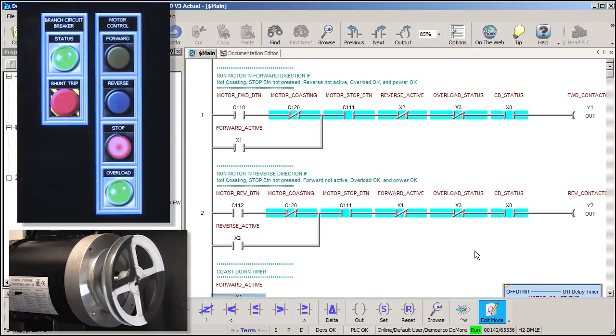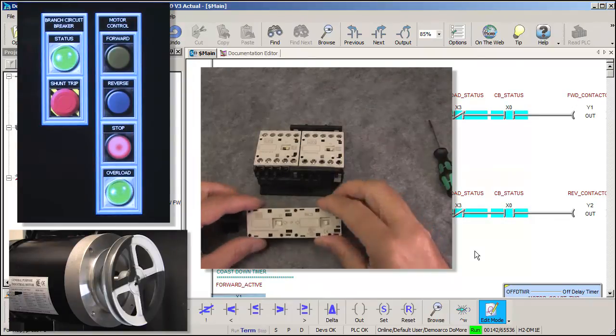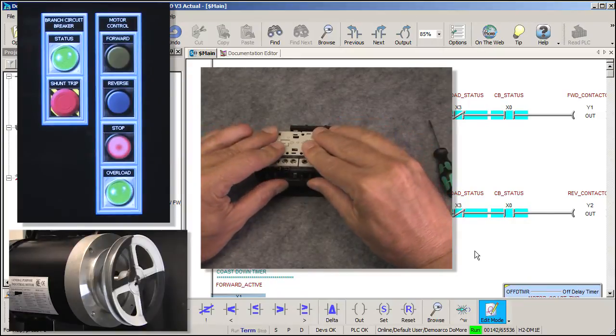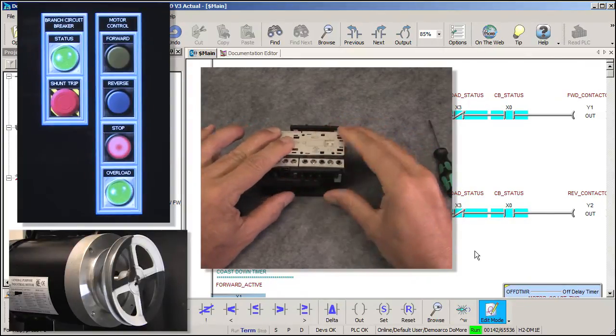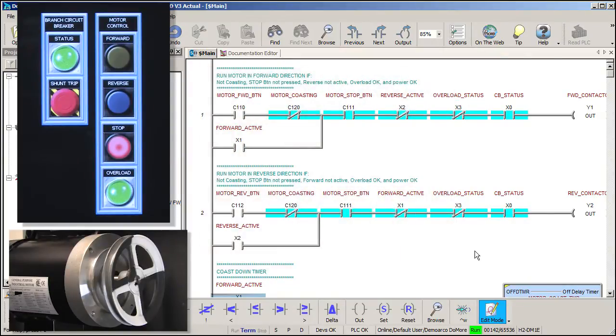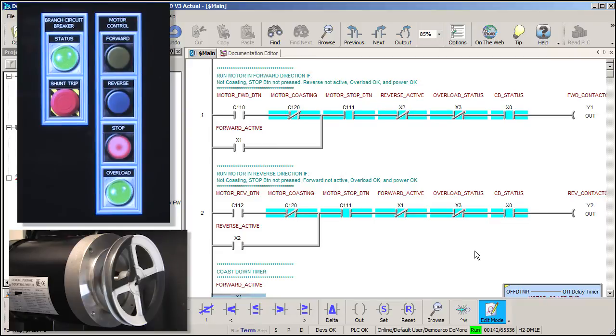Well, not really, because it physically can't happen in this system. Remember, in the hardware video, we installed a mechanical interlock to prevent just this scenario. It physically won't allow two contactors to engage at the same time. Because of that, one of the aux contacts can't close, so that circuit will never seal or latch.